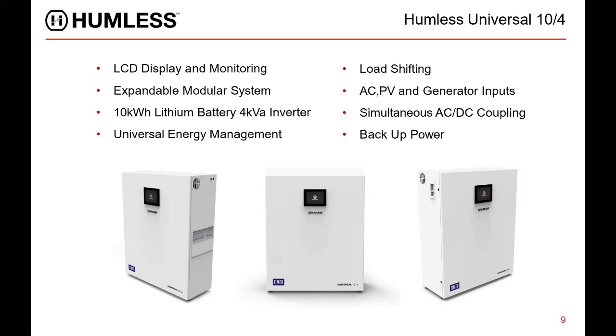So that's my AC coupled device. I have a very small west pitch where I couldn't fit much, so it's really only another K. It's 3 panels on the west pitch. That's my DC coupled array. By using those two together, if I have a grid outage, that AC coupled array can still be converting amps and filling batteries, but it also will run loads in sunlight conditions without microcycling the storage unless needed.